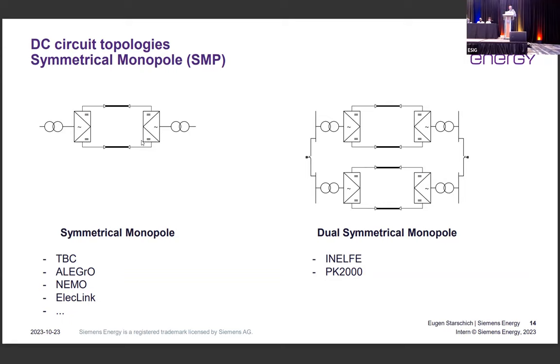So the power limitation is not due to the converter design itself, but mostly due to the single contingencies that we see in the AC grids. If we have a single contingency in the AC grid, then the power of this converter should not be higher than this single contingency. This is why the limit we see in the market is right about 1.3 gigawatt, which is the maximum single contingency limit in many areas, also here in the US.